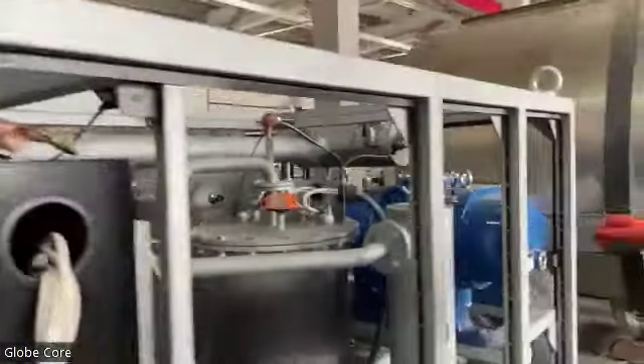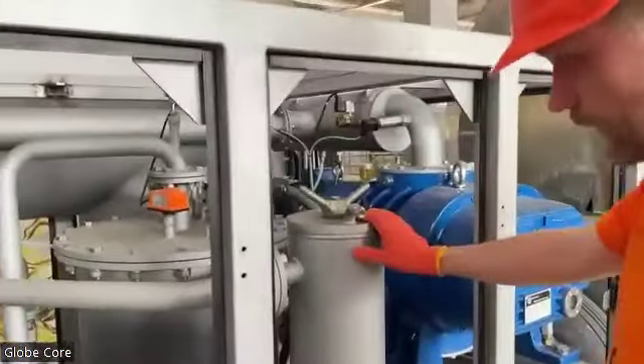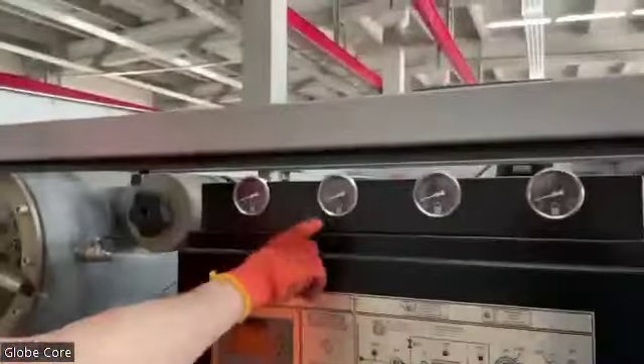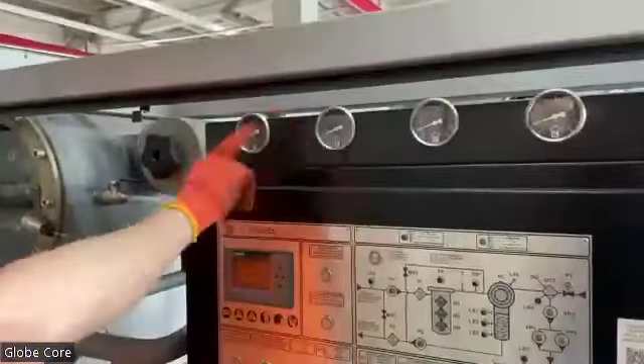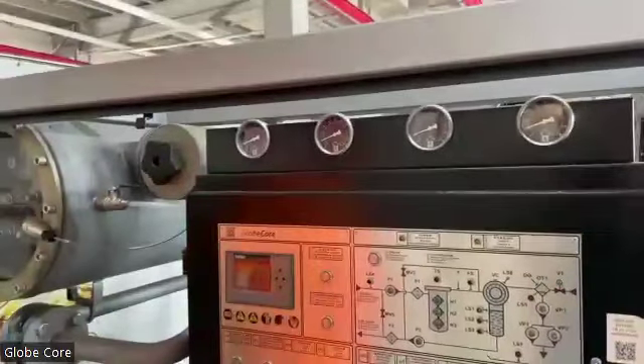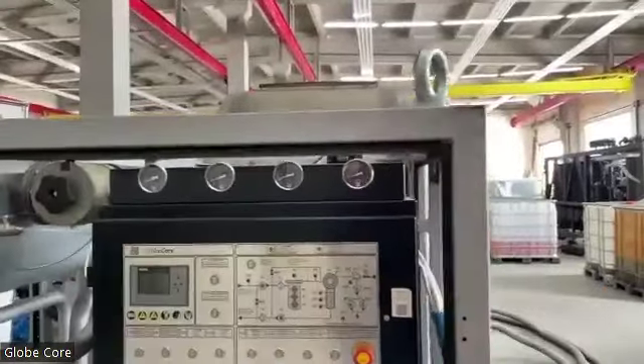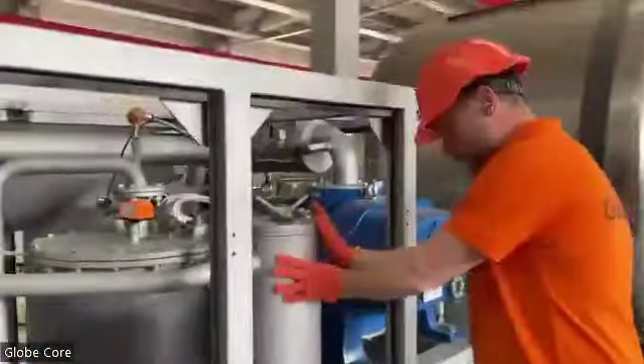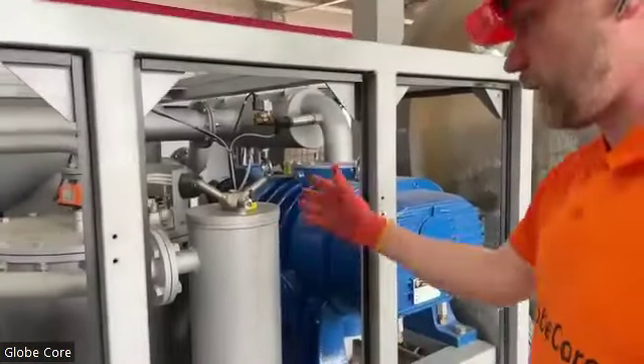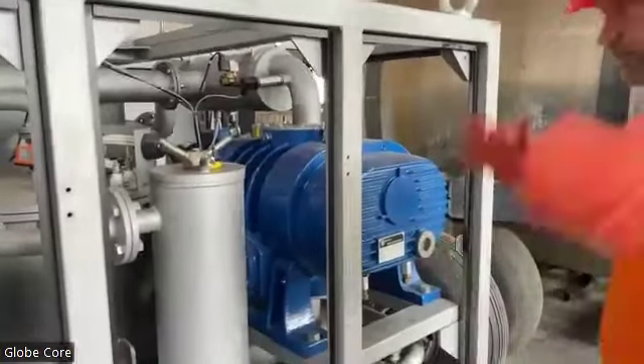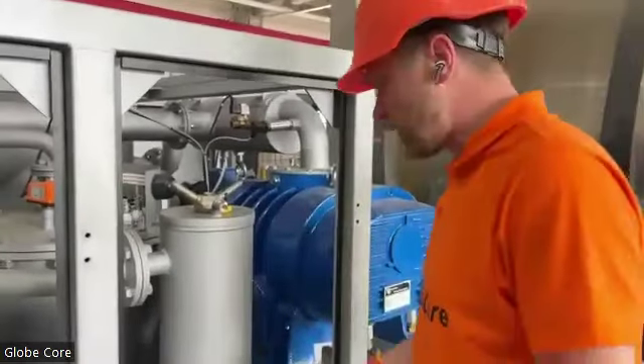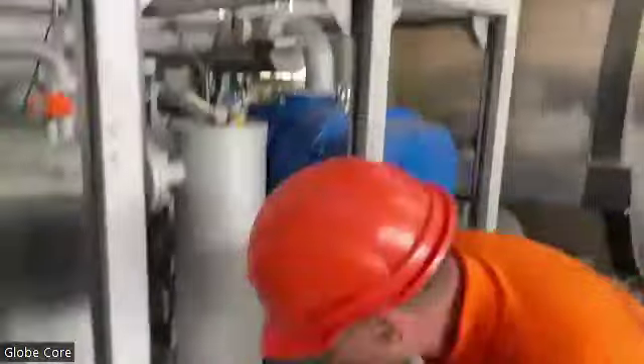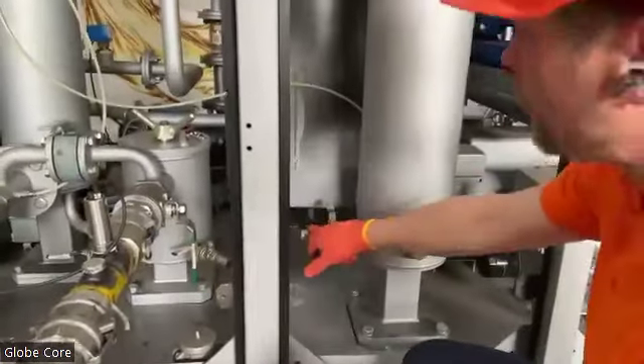Then we have the fine filter. Then we have another port for another gauge. So for each filter, we have two gauges. One at the inlet of the filter, second one at the outlet. So by the differential pressure on these gauges, we can judge the state of the filtering elements. So the fine filter, usually it is 25 microns, but again, any size can be supplied according to the client's requirements. What we have in here also, here we have the draining point to drain oil while servicing the filter.